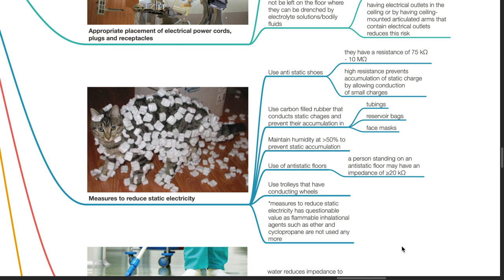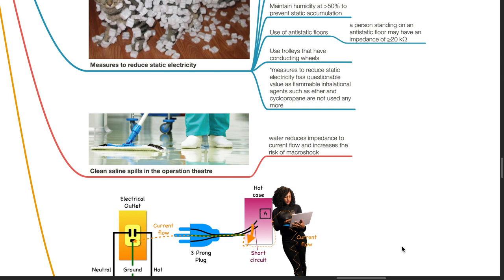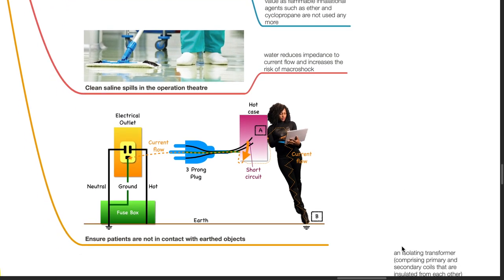Measures to reduce static electricity have questionable value as flammable inhalational agents such as ether and cyclopropane are no longer used in modern operation theaters. These measures include use of anti-static shoes with resistance of 75,000 to 10 megaohms that prevent accumulation of static charge, use of carbon-filled rubber in tubings, reservoir bags and face masks, maintaining humidity above 50%, use of anti-static floors with impedance over 20,000 ohms, and use of trolleys with conducting wheels. Clean saline spills in the operation theater as water reduces impedance to current flow and increases the risk of macroshock. Ensure patients are not in contact with earth objects.